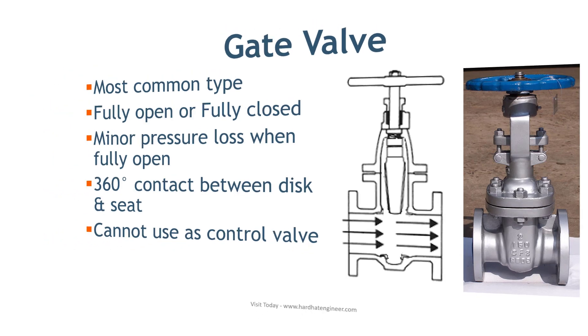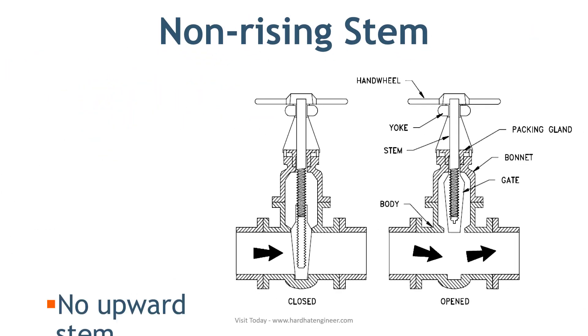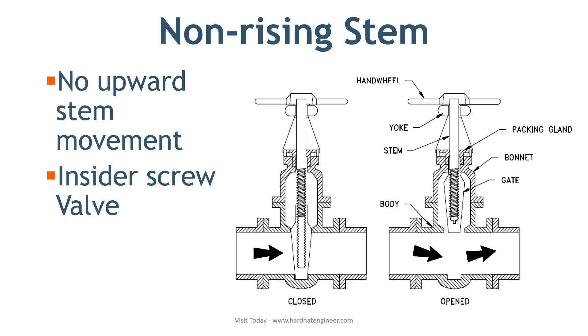Gate valves have either a rising or non-rising stem. A rising stem provides a visual indication of valve position because the stem is attached to the gate in such a way that the gate and stem rise and lower together as the valve is operated. A non-rising stem valve has a pointer threaded onto the upper end of the stem to indicate the valve position, since the stem does not rise or lower when you operate the valve. Non-rising stems are used underground or where vertical space is limited.